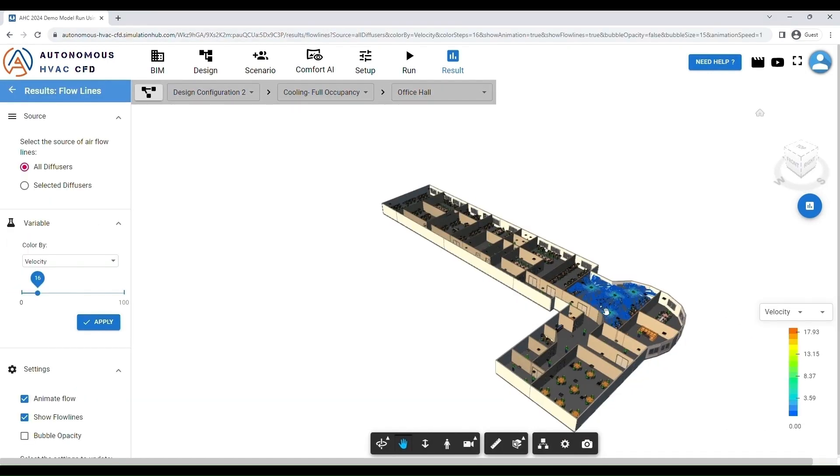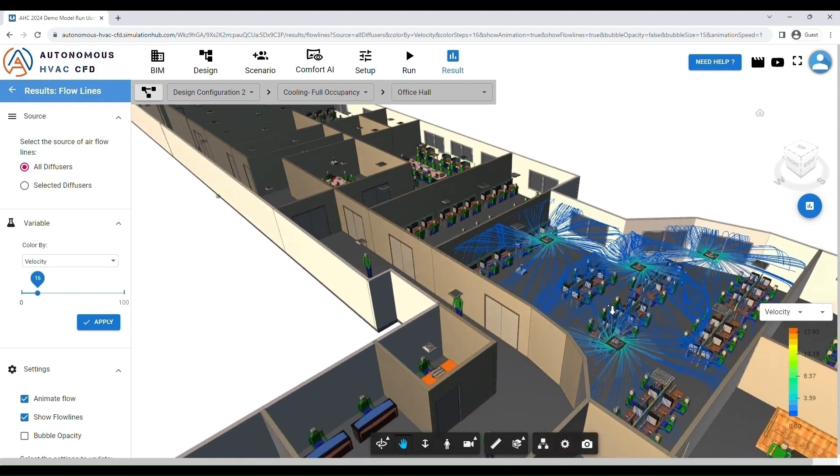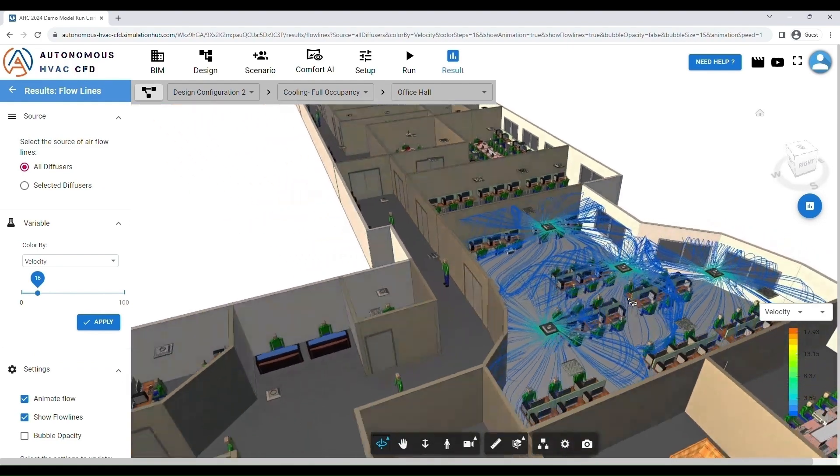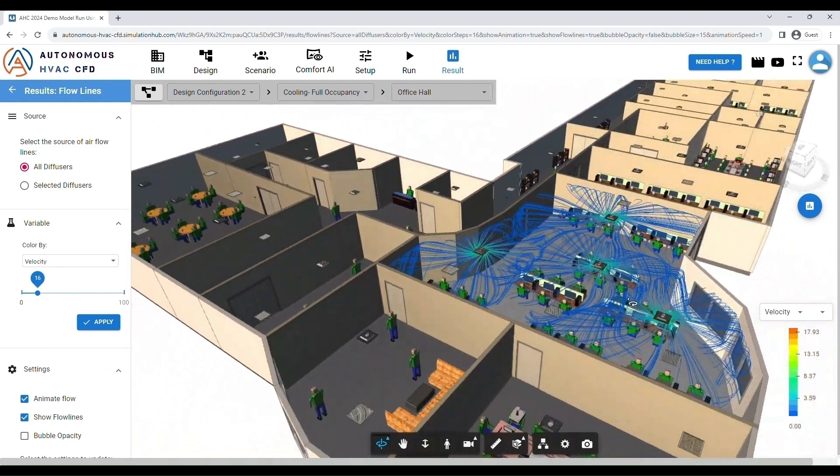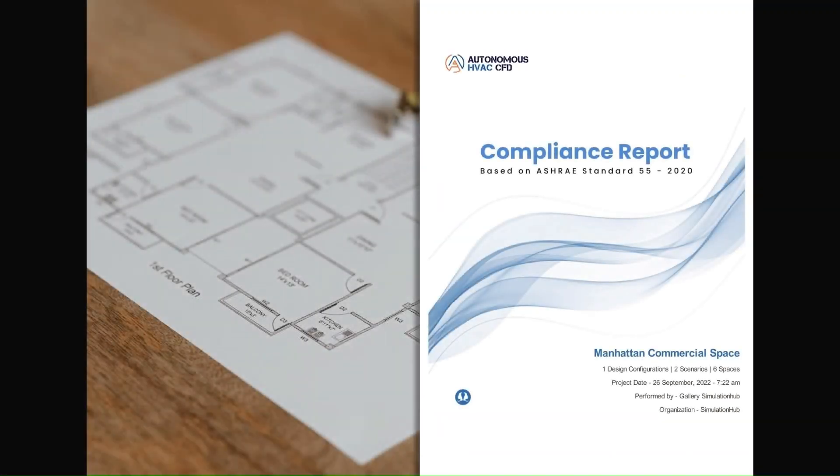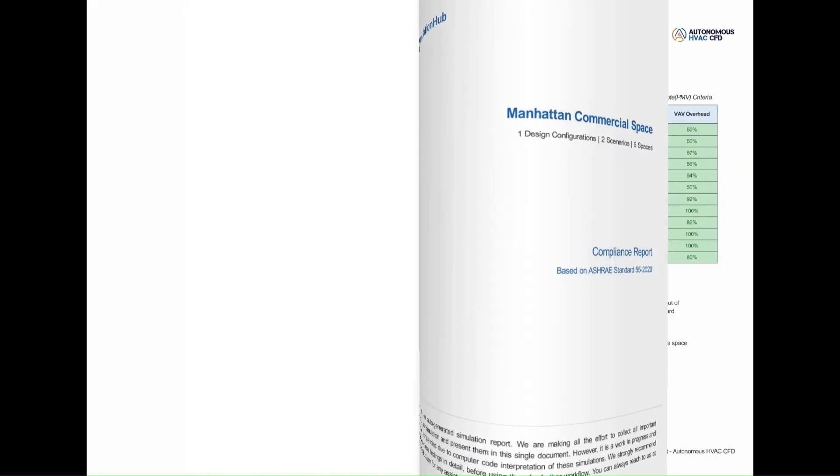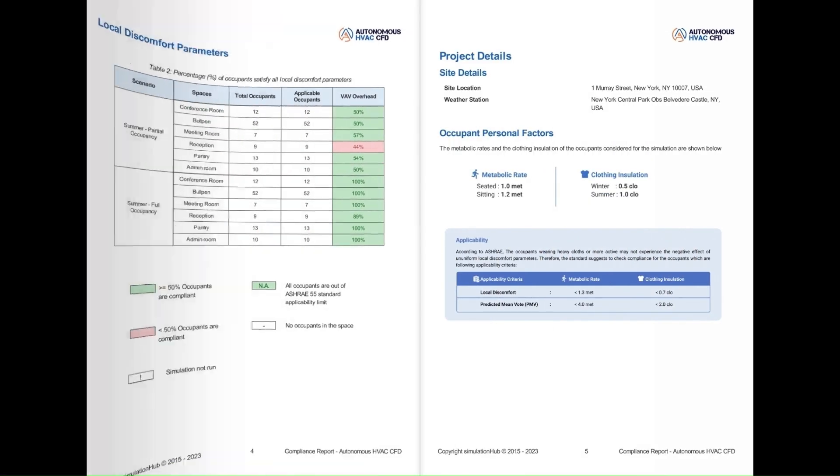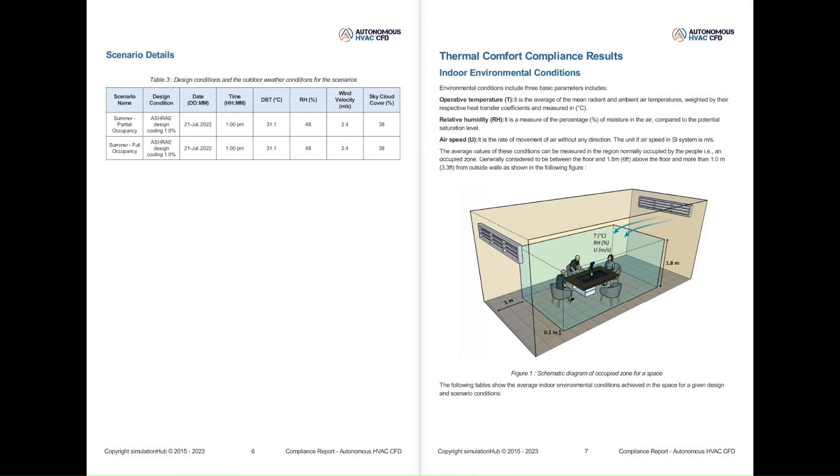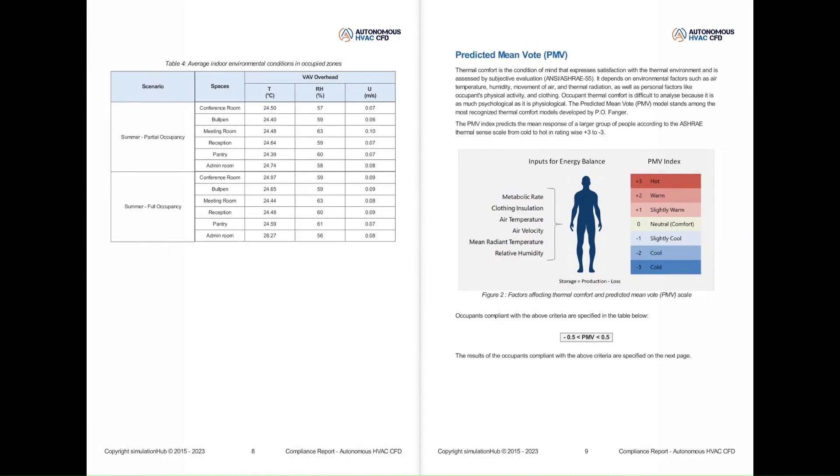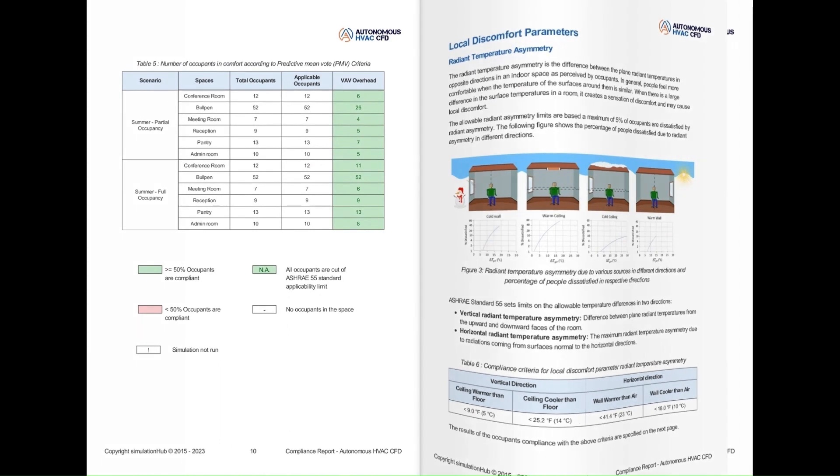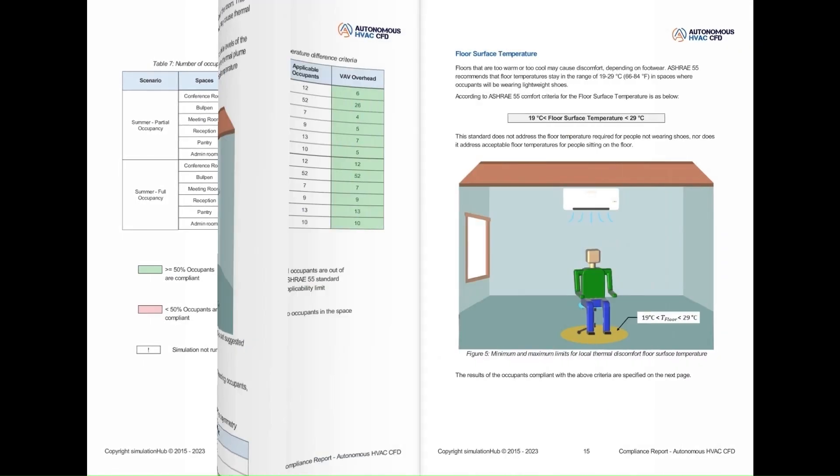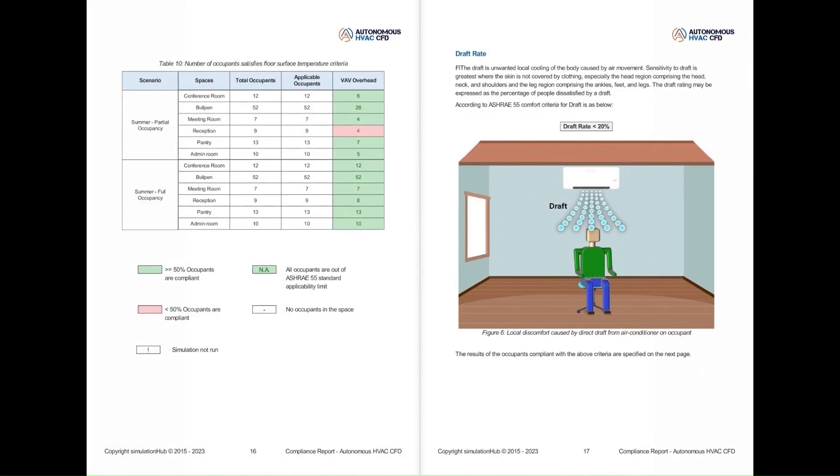Cast light on invisible airflow patterns through the flow lines visualization. Receive a compliance report on ASHRAE Standard 55, assessing compliance with PMV and local thermal discomfort including radiant temperature asymmetry, vertical temperature difference, draft, and floor temperature for each design.